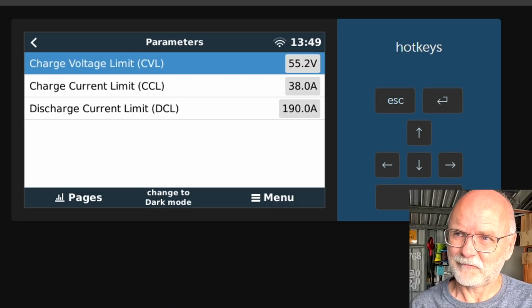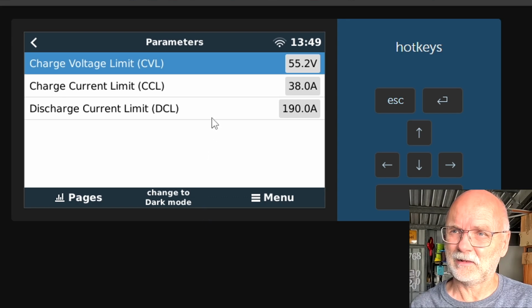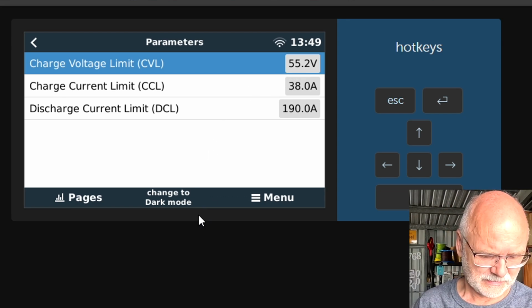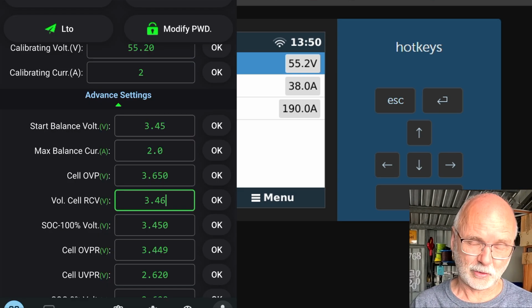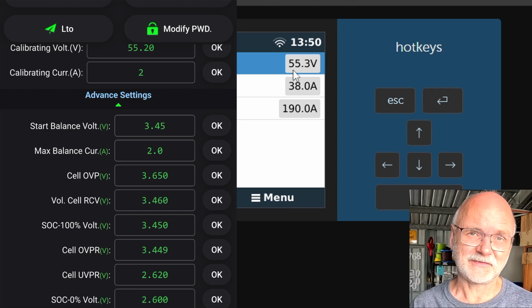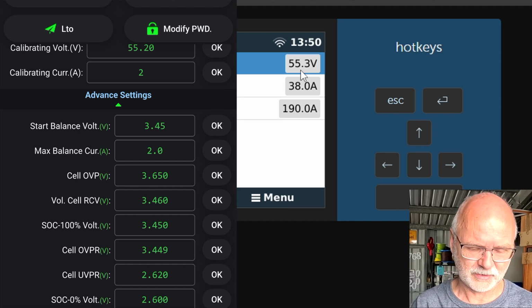So, my friends, it is now half an hour later, and the CVL, the charge voltage limit, is still on 55.2. Nothing has changed. And also, if I change the RCV voltage in the JK BMS to 3.46 volts, for example, and click OK, we can see the CVL in the Victron system goes up, as it's supposed to do. So it obviously still listens to the RCV. I wonder if the timer is not triggered anymore for whatever reason.